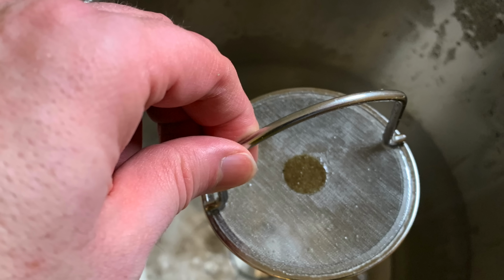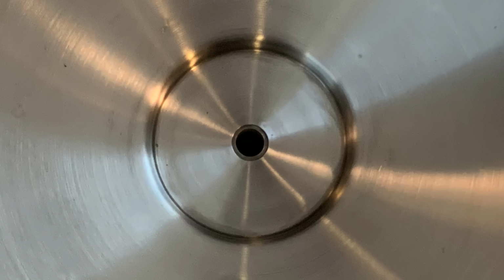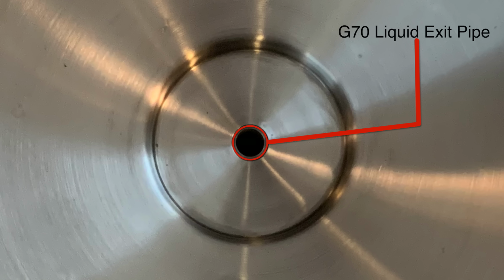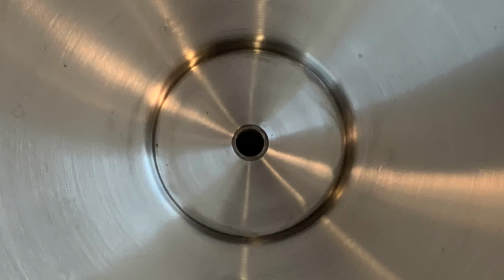After much time was spent looking at this problem, I was amazed to find out that the very small amount of debris on this filter is enough to choke the pump. This is because the small pipe underneath is exactly this size in circumference, and the pump's suction pulls the filter into a seal, meaning the filter sits very tightly to the pipe below.